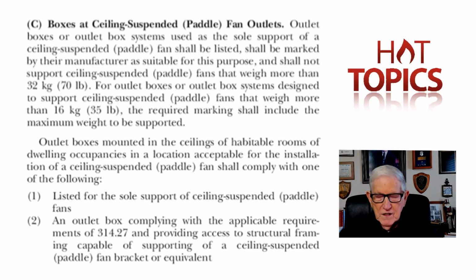Number one, listed for the sole support of a ceiling suspended paddle fan. That's what would be mounted to it. Number two, an outlet box complying with the applicable requirements of 314.27 and providing access to structural framing capable of supporting a ceiling suspended fan bracket or equivalent.